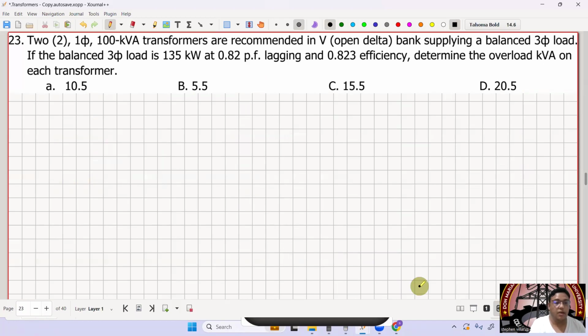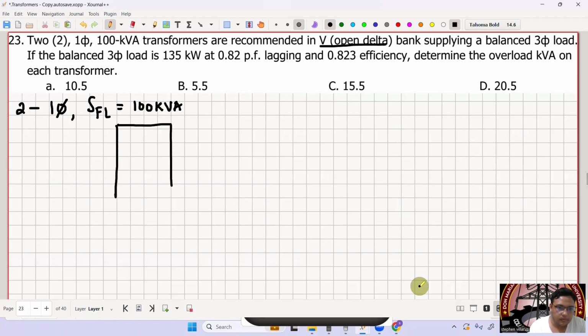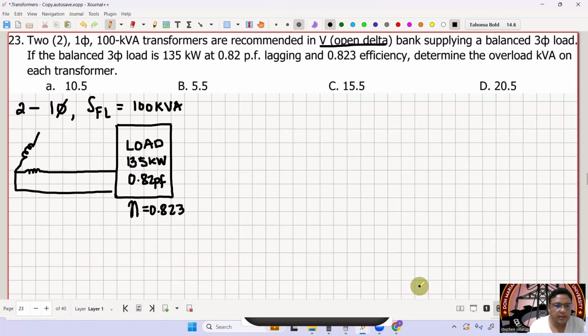Okay, next tayo. Number 23. So dalawang single phase transformer that is having a rated power of 100 kVA are recommended in open delta bank supplying a balanced three-phase load. If the balanced load, so yung load natin dito is 135 kilowatt at 0.82 power factor, and yung efficiency natin dito sa load is 0.823. So, determine the overload kVA on each transformer. Okay. Take note po, ma-overload to.